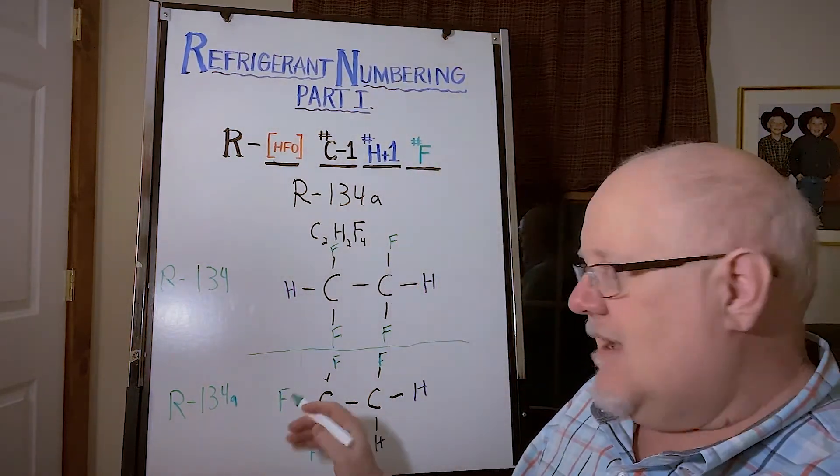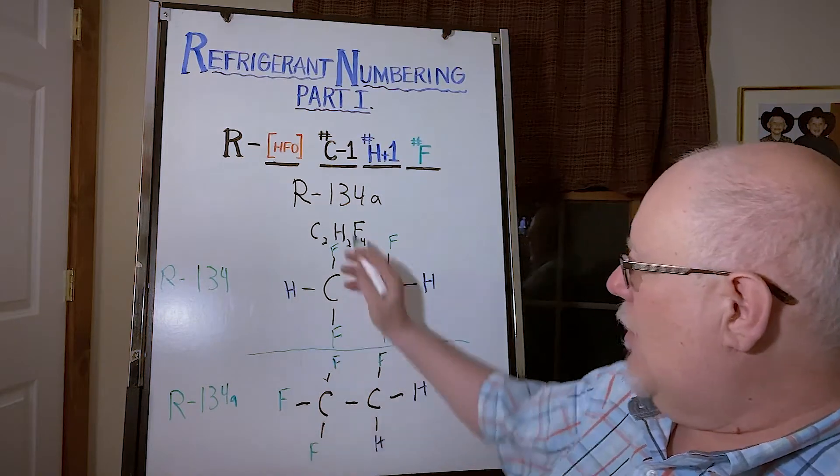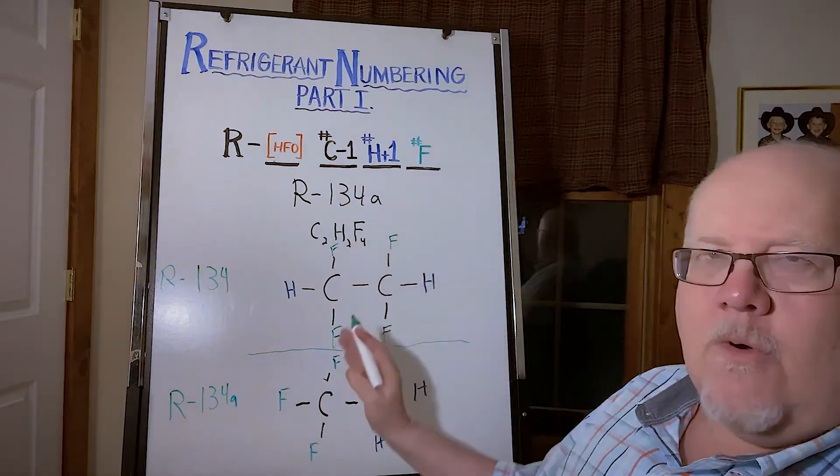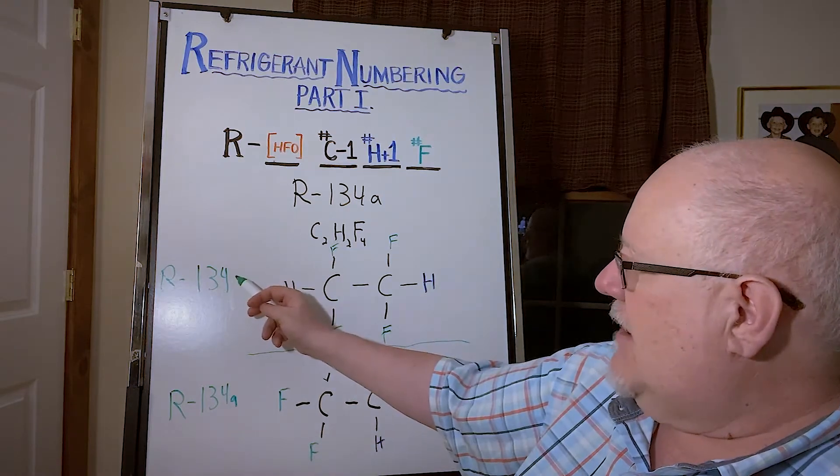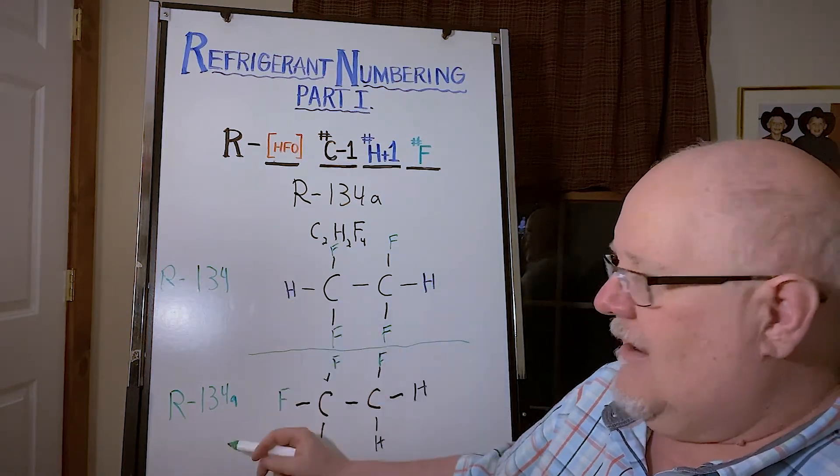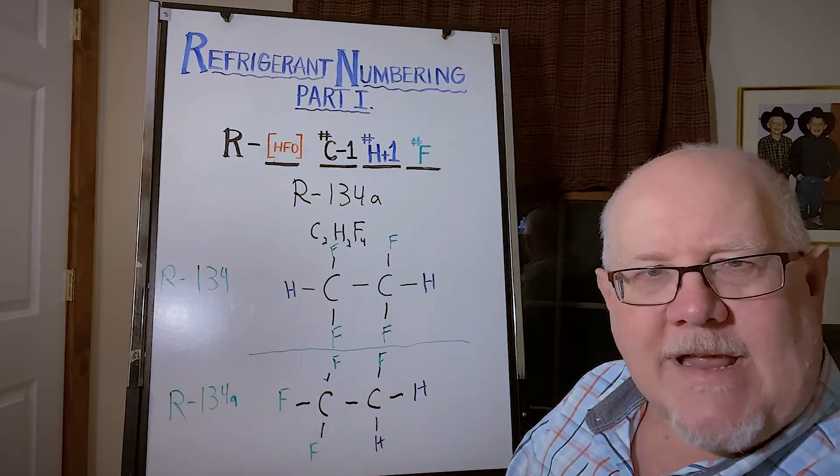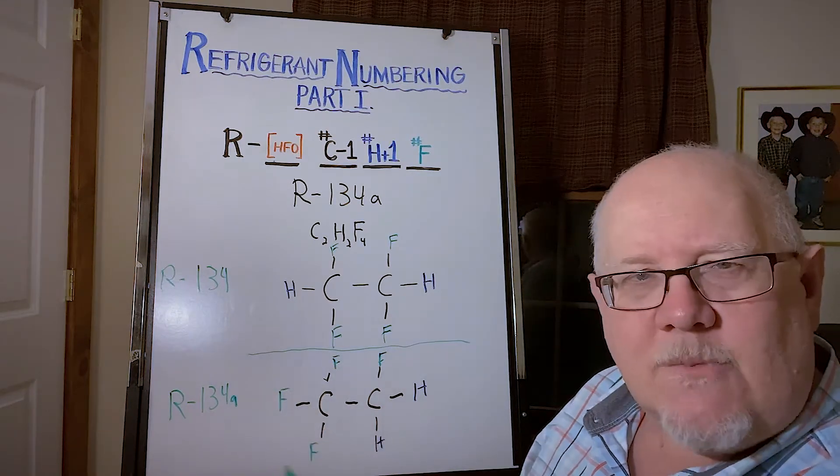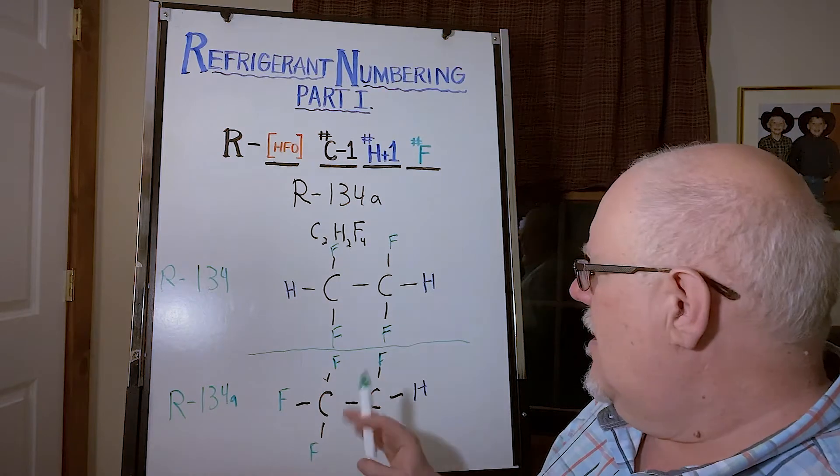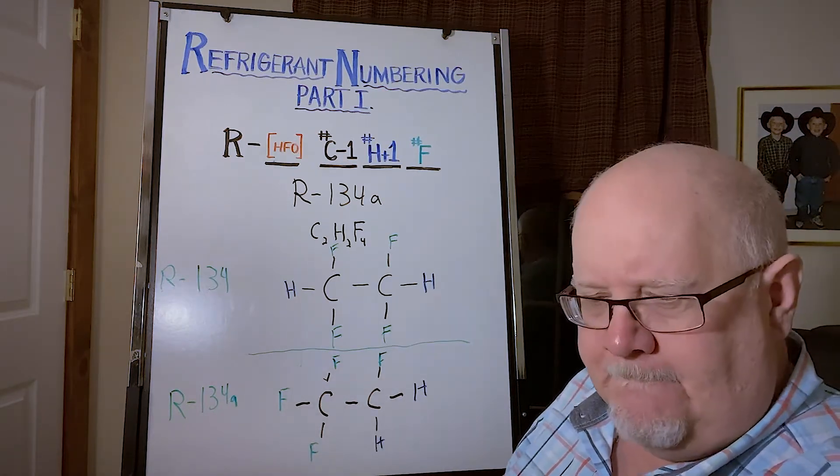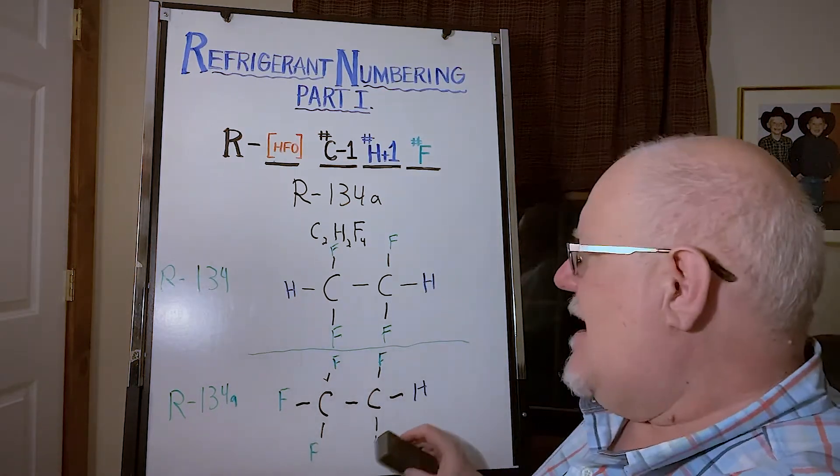So the way the system works is that gets the nominal number, so this would be known as R-134. And then another arrangement with the same formula but a slightly different arrangement is going to get the lowercase 'a' designation. They're both C2H2F4, different isomers or different arrangements, least to most symmetrical going down. If there was another way to arrange these that was even more unbalanced or more unsymmetrical, it would be 134b. In this case that's not possible, but that's where we're at.